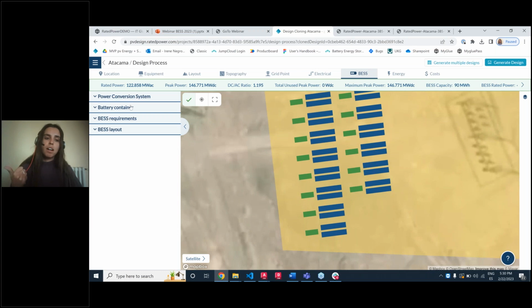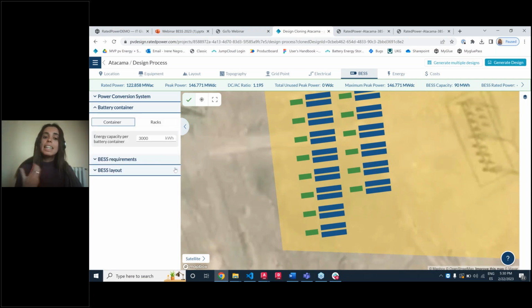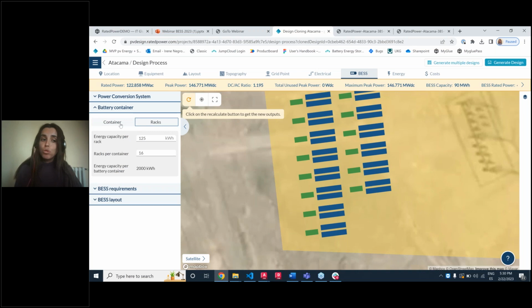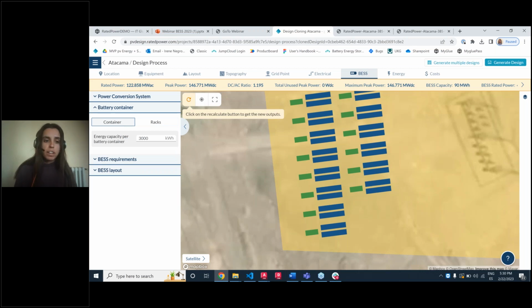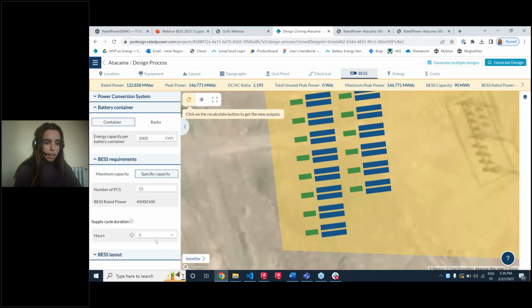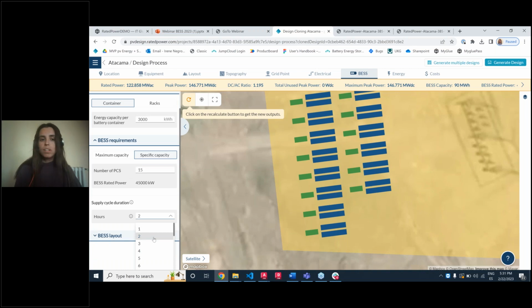Once we have set our power conversion system, we can also include the capacity of our container or racks, depending on the solution you will be using for the battery. For example, if we set the capacity per container at 3 megawatt hours, this is why regarding the hours of supply duration we have 1 hour, 2 hours, 3 hours, because it's directly related to the power and capacity of our equipment. Once we have set both the power and capacity of our containers, we size our battery system based on the number of containers we would like to include.